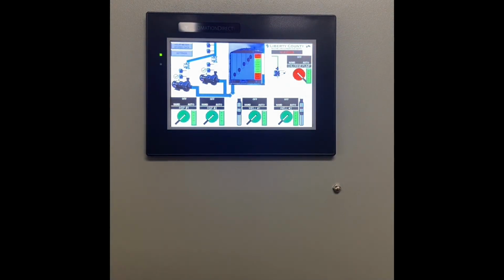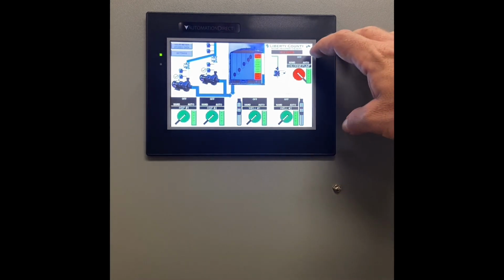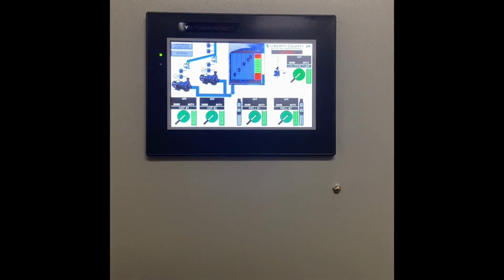There's my contactor. You'll notice that the green light, or green piping rather, is now fully green. So we are getting feedback from contactor C1 stating that that pump is indeed working. Now, if the pump is disconnected externally to this control panel, then you will not be getting chlorine, but you will be getting indication as such. But that's outside the realm of this control project. We'll go ahead and put it back in auto now, and you'll notice it goes back to the same state.